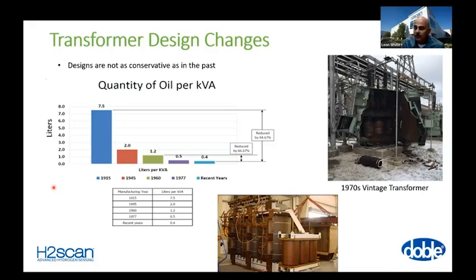So a manufacturing issue that may not have been a problem in the 1950s or 60s can cause a transformer failure very quickly today. And maybe Tony has some data on infant mortality, but my feel is that, I was working with a utility that was replacing transformers. They were 60-year-old transformers because they were worried that they were going to fail. And the new transformers, some of them failed on startup.